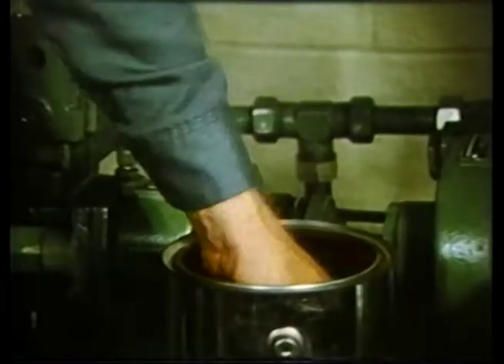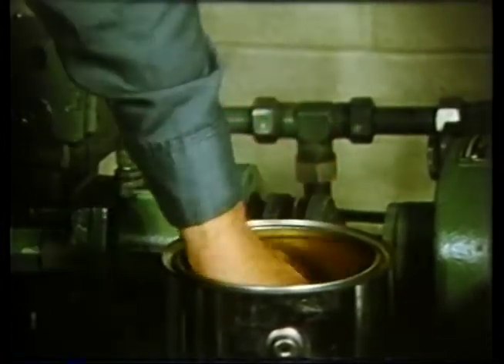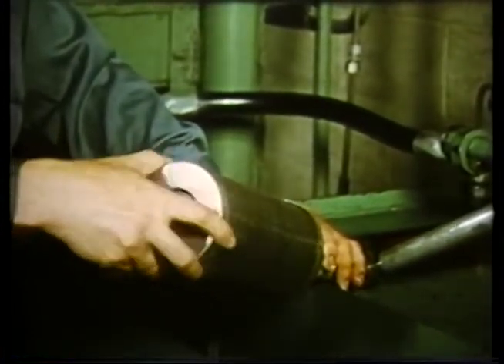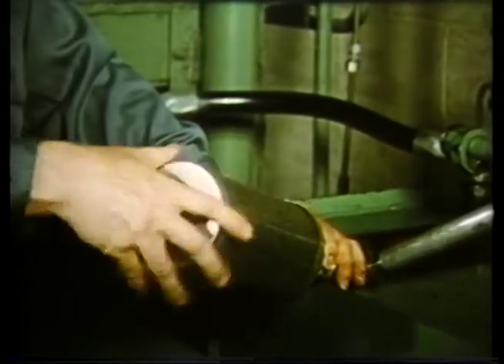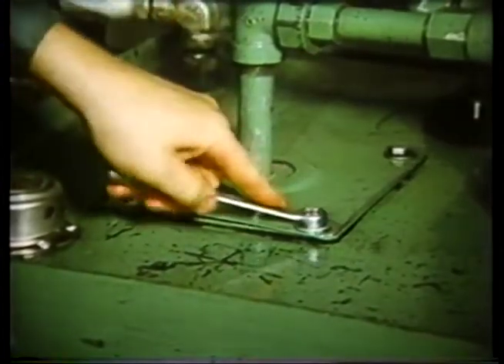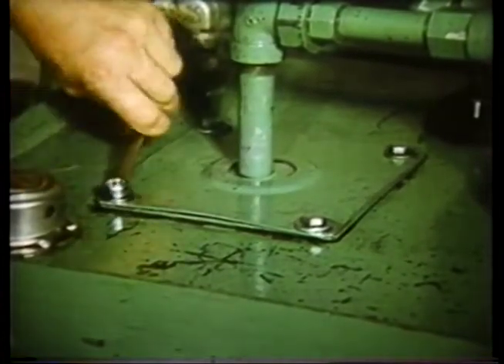The interior of the reservoir should also be cleaned. Be sure to remove all sludge, dirt, grit and lint. Check the air breather filter — make sure it is clean or replace it. If the suction strainer is located in the reservoir, clean or replace it. When reassembling the reservoir, make sure that all covers fit well, that gaskets are in place and that all bolts are pulled down tight.